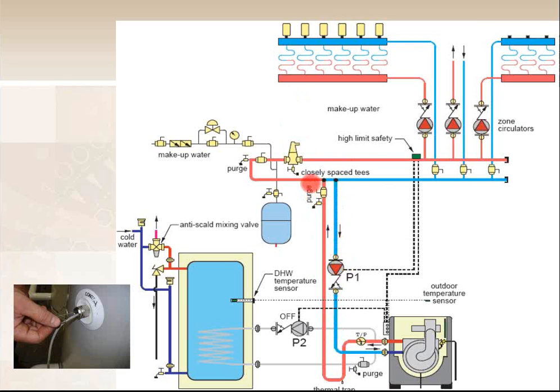These closely spaced T's, these are 2 T fittings. Put them as physically close as you can get them. If you can physically connect them to each other, all the better. Kind of the rule of thumb is you don't want to be any more than like 3 to 5 pipe diameters away from each other. So if you got 2-inch pipe, these 2 T's should be no more than 10 inches apart, right? That's kind of the rule of thumb.